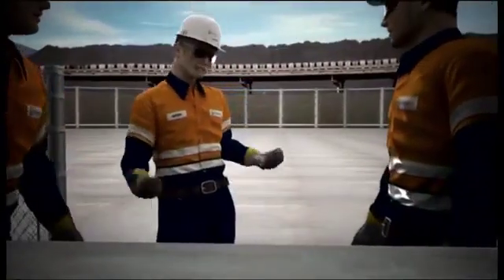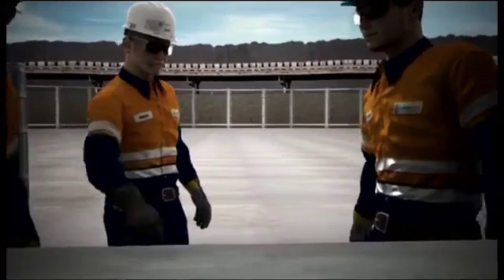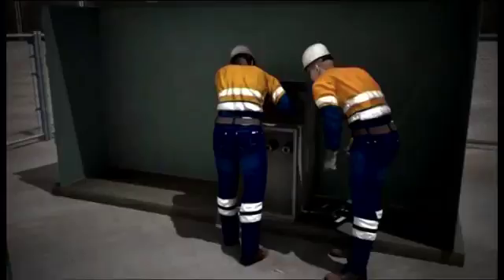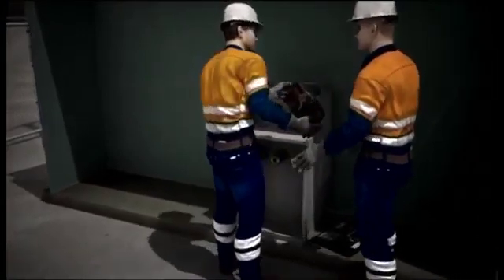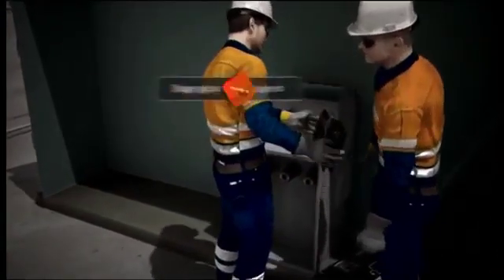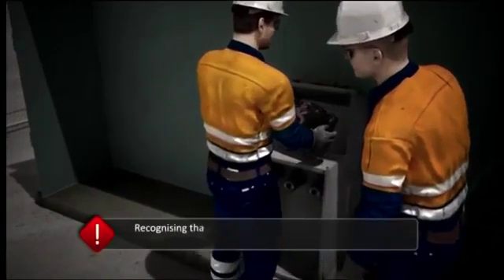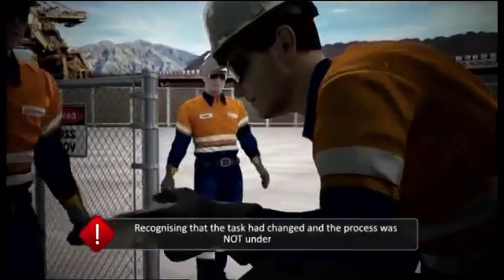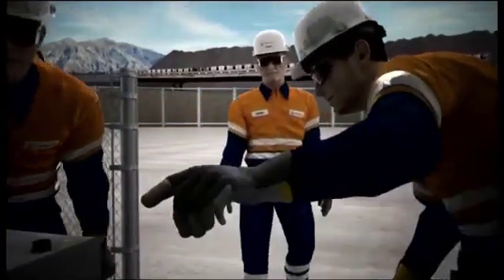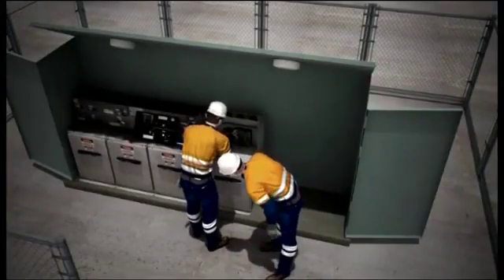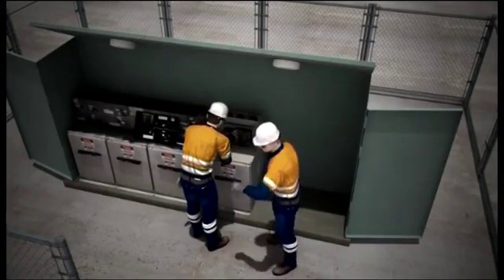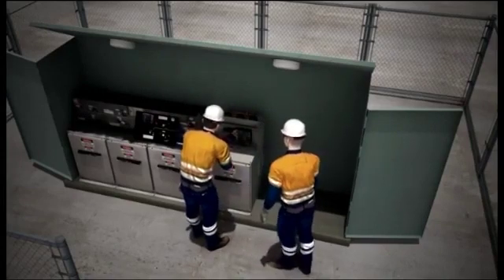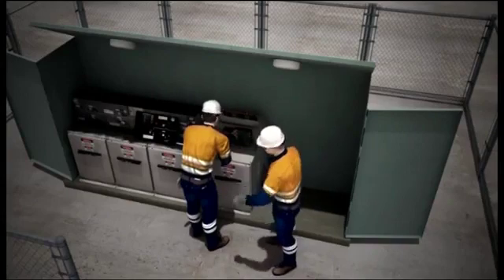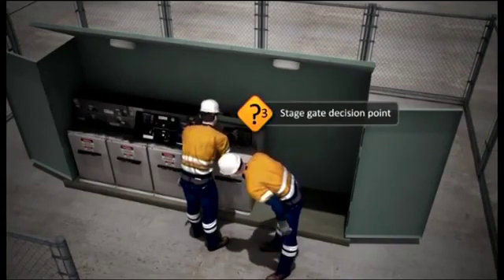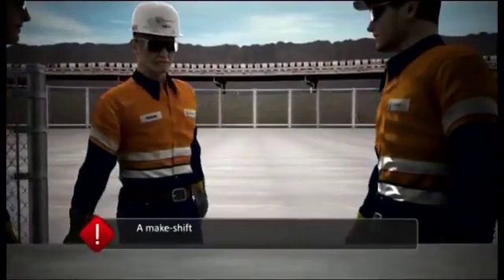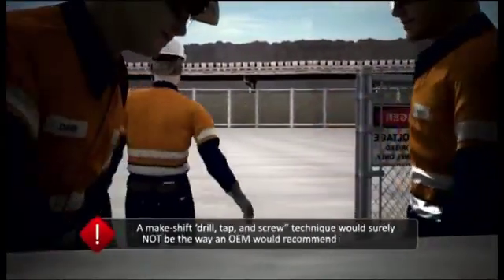The workings of the switching mechanism are a complex and unfamiliar task. This became more evident when the springs on the second mechanism fell apart on removal. This was the second decision point where the job should have been stopped, recognizing that the task had changed and the process was not under control. To keep the springs compressed on the third mechanism, Dave used a makeshift drill, tap and screw technique to make up for his lack of knowledge of how the high voltage isolation mechanisms worked. Yet another decision point where the job should have been stopped. Surely this would not be the way an OEM would recommend it to be done.